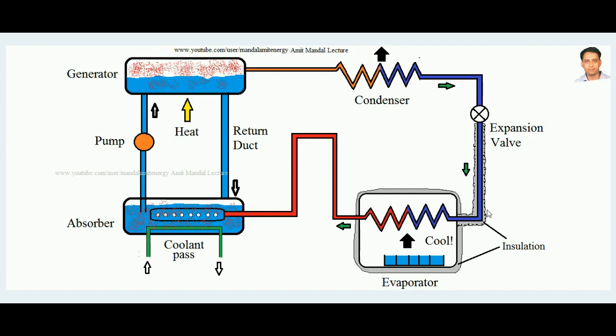This high-pressure ammonia is sent to the condenser, where it liberates heat and comes out in liquid form. The condensed ammonia then passes through the expansion valve and through the evaporator, where it absorbs heat and becomes vapor again. This vapor goes back to the absorber, mixes with cold water, is pumped to the generator, and is liberated again — completing the cycle.